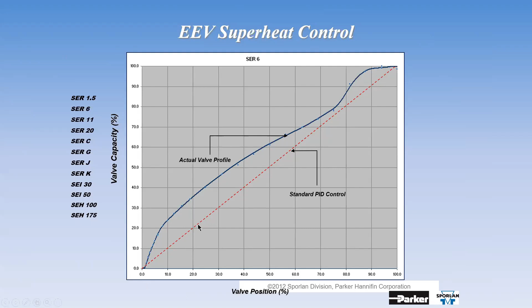And there's the case controller for you. Just like a mechanical valve, we're taking a true pressure temperature superheat. At the same time, we can take a look at the temperature coming off the coil. Also, when it's time to defrost, certain manufacturers tell us this probe has to go at this spot because we know this spot gives us the best reference for defrost termination. So we have a defrost termination sensor, and we do have space on here for a fourth temperature if you want to do product simulation temperature. If it is required in your locality, we have a fourth auxiliary input where you could do a product temperature input. So not only do you have the superheat, not only do you have the temperature coming off the coil, not only do you have temperature defrost termination, but you've got the simulation temperature, okay, for that case. Any questions on this at all?